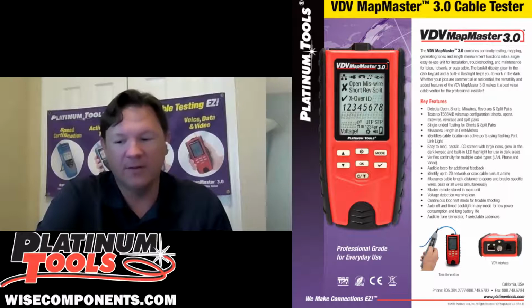Well, as we talked about with the prepping of the cables and termination of the cables, it doesn't matter how many years a technician's been out in the field. I know they all think they do their work correctly every single time, but people do make mistakes. And one of those mistakes is easily the biggest problem we see on a cable. If there's a failure on a cable, it's the termination of the connector on the cable. Right. For over 80% of the time, that's what it is.